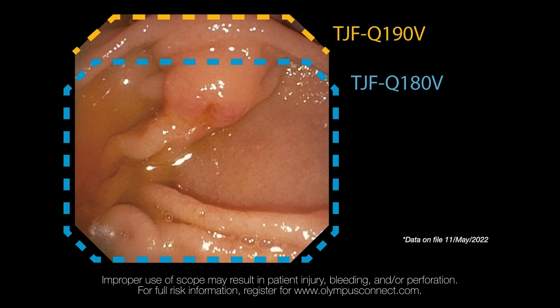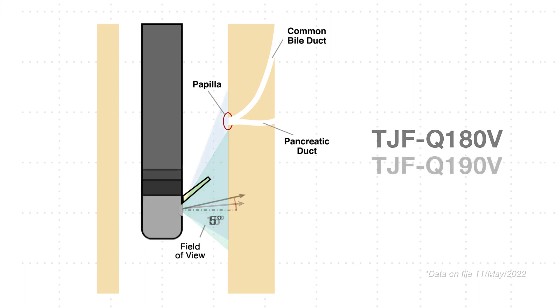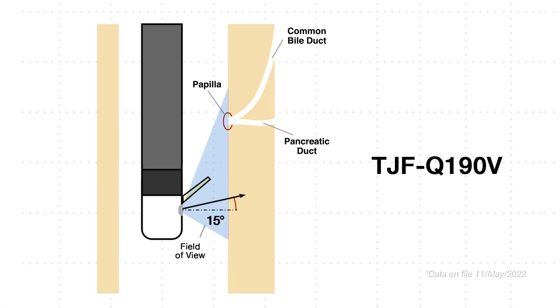The TJF-Q190V utilizes a square image and 15-degree backward viewing that allows for a more optimized and expanded field of view. The 180 scope, on the other hand, had more of a horizontal view. This expanded vertical view is important to aid in safe and atraumatic cannulation. It is important to know where the papillary orifice is, but it is equally important to know how large the intra-duodenal part of the papilla is, how many folds there are, and where the papilla meets the duodenal wall.